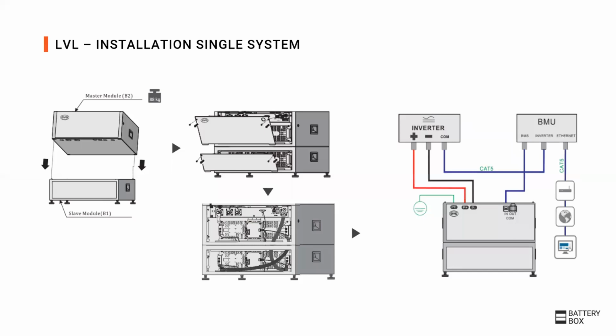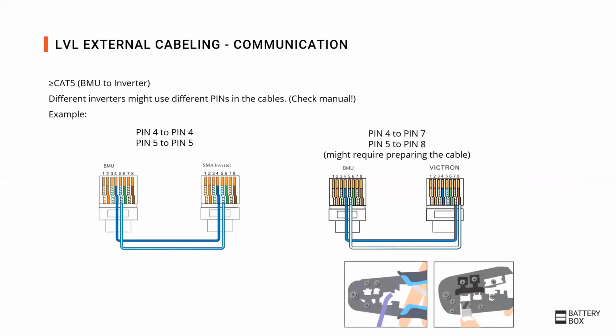For the installation, the upper and lower battery modules are stacked on top of each other. Unlike the premium HVS, HVM, and LVS, the LVL requires some internal cabling. Therefore, the cover is removed. Then the cabling can be done. It is important to make sure not to make a short circuit and connect all cables correctly and according to the manuals. The communication cable from the LVL goes to the BMU and from the BMU to the inverter.